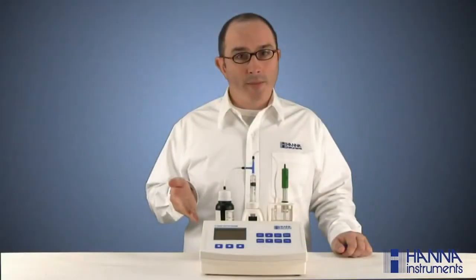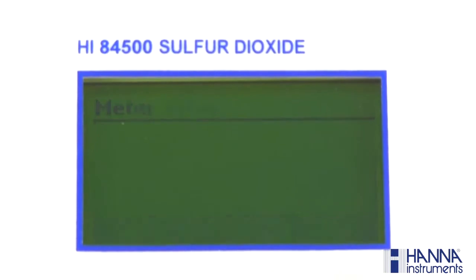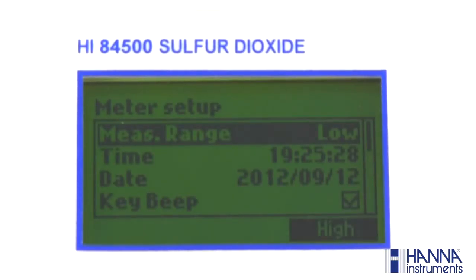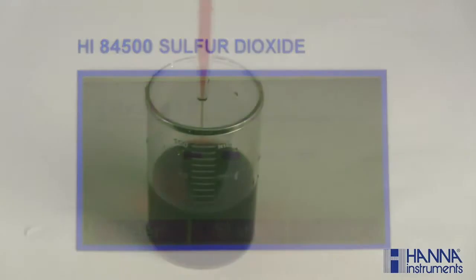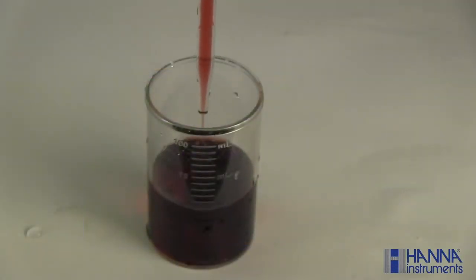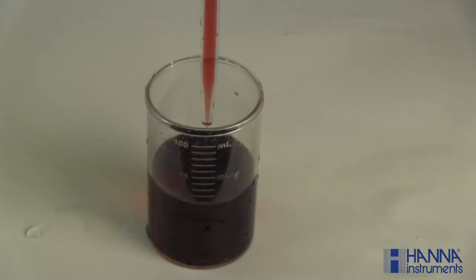Now that the instrument is set up, it's time to measure a wine sample. Press Menu, then Setup to select the range for measurement. Again, we'll be performing a low-range free sulfur dioxide measurement right now. Ensure your pump is primed and calibrated with the correct titrant. Using a clean pipette, precisely add 50 milliliters of wine sample to the 100 milliliter beaker. The volume of wine added is critical for an accurate measurement.